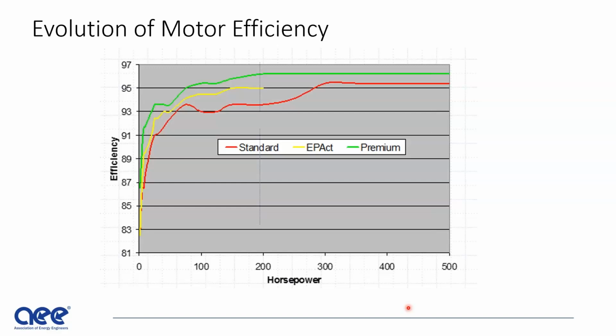So the evolution of motor efficiency, you see in the chart. The red chart is the standard efficiency curve. EPAct went to 200 horsepower, and you can see that in the yellow. And now with the new DOE extension to 500 horsepower, you see the green and the efficiency of motors today.